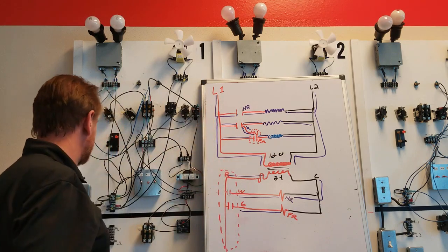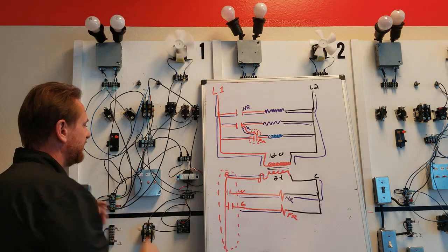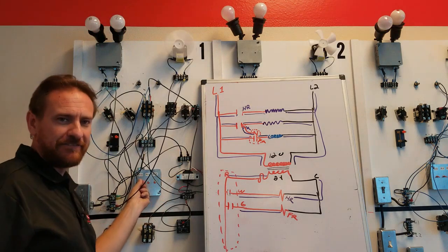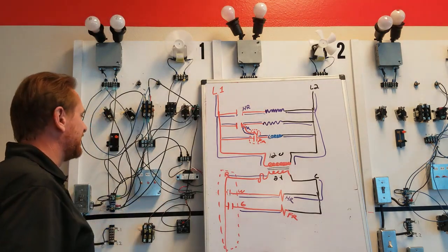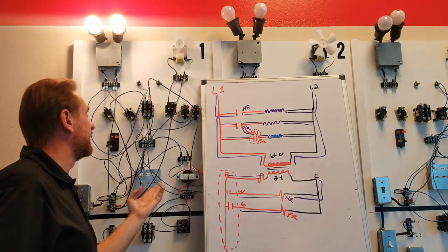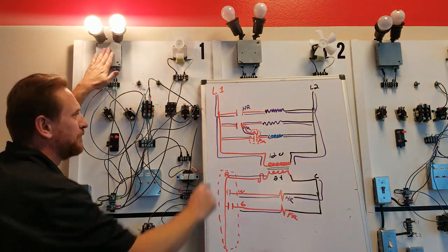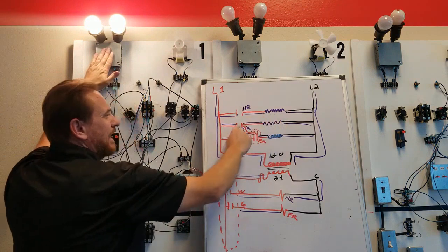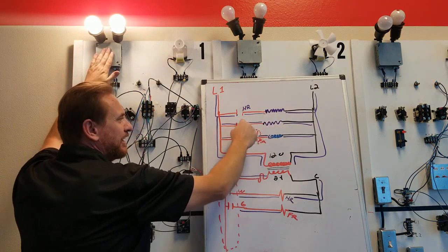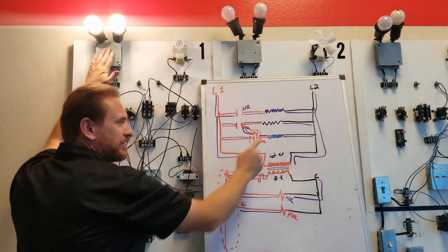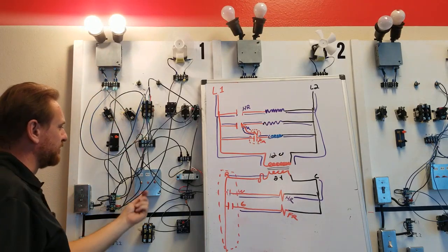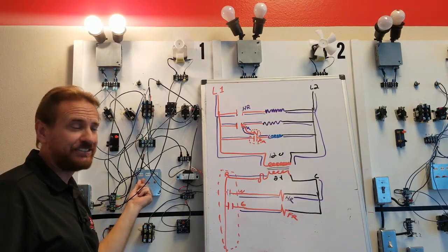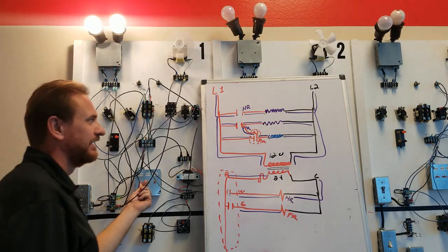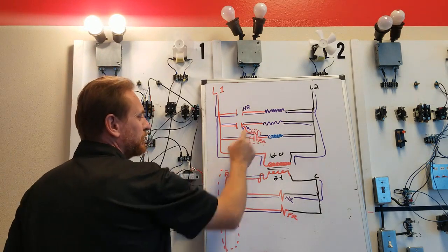So now, if I turn this on and have a call for fan, my fan comes on independently. But if I have a call for heat, thermostat calls for heat, connects R to W. I pass power to this heater, and it goes through the normally closed connections, energizing my fan. And if I turn my fan on to the thermostat, it stays on. If I cycle it off, it still stays on because it's going through this normally closed.